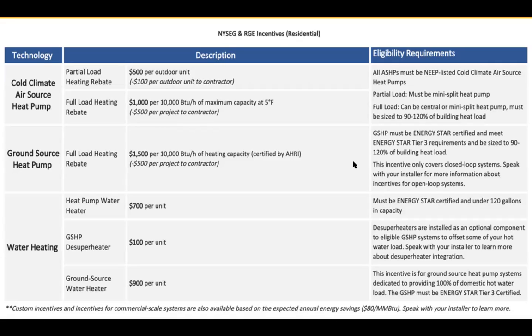For air source heat pumps, if you do a partial load, remember I mentioned you can have just one or two rooms, you get $500 per outdoor unit, a portion of which goes to the contractor, unless the contractor chooses not to take that, which is the case with ours. Or if you do a full load, it's $1,000 per 10,000 BTU hours of maximum capacity at 5 degrees Fahrenheit. That's a pretty obscure number. As a rule of thumb, the average house is about 40,000 BTUs, but don't remember that number, because you don't know how many BTUs you need unless you're an engineer or have had a heat load calculation done. That's why we sometimes hesitate to give numbers, because they may not be your numbers.